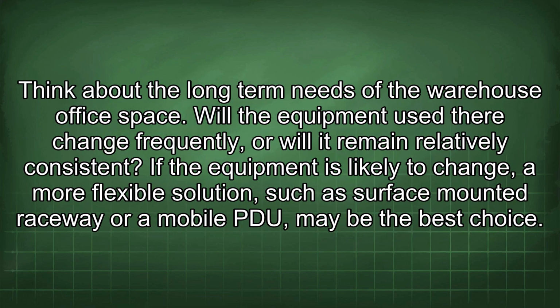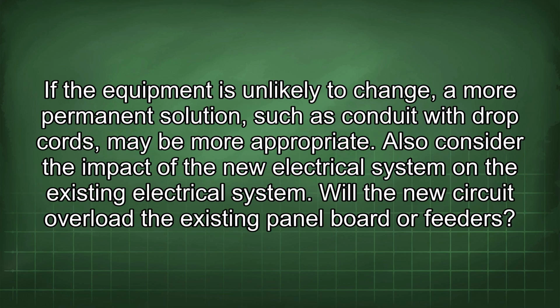Think about the long-term needs of the warehouse office space. Will the equipment used there change frequently, or will it remain relatively consistent? If the equipment is likely to change, a more flexible solution, such as surface-mounted raceway or a mobile PDU, may be the best choice. If the equipment is unlikely to change, a more permanent solution, such as conduit with drop cords, may be more appropriate.